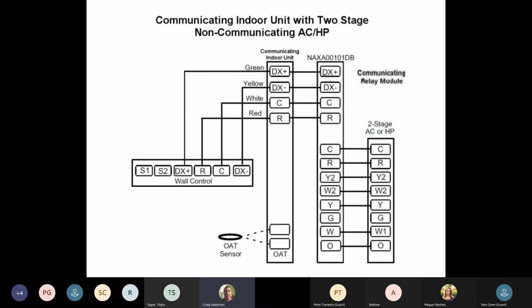If we have a communicating wall stat and a communicating indoor unit and the customer has an existing heat pump or a 2-stage air conditioner, we need to add another board because it's 2-stage and it's heat pump. We need to add a communicating relay to that furnace downstairs so everything will talk properly, and we need to add an outdoor sensor. We're adding an outdoor sensor because old units, most of the older ones, don't have outdoor sensors. So we need to add one so the stat can read the temperature outside. So be mindful of that as well.